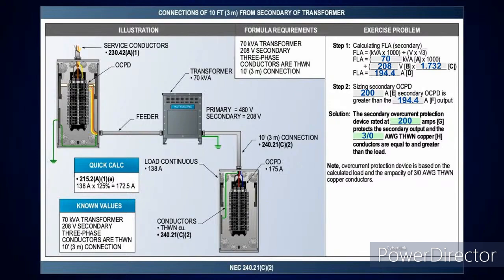So when you look at this, all you're going to do is, like we've done before, treat it just like we do a transformer calculation. You remember I did a presentation on here where I went through and showed how to calculate transformers. This is the same thing for sizing your conductors. All you needed to know was the kVA of the transformer, multiply it by 1,000, put it in VA. Then you take the voltage. In this case, it's a 208 volt three phase, so I multiply the 208 volts times 1.732, which gives me 360, and I divide that into the VA of the transformer, which gives me 194.4 amps.